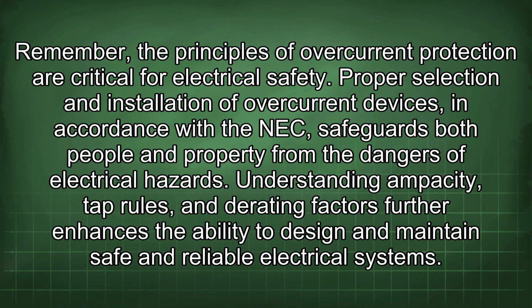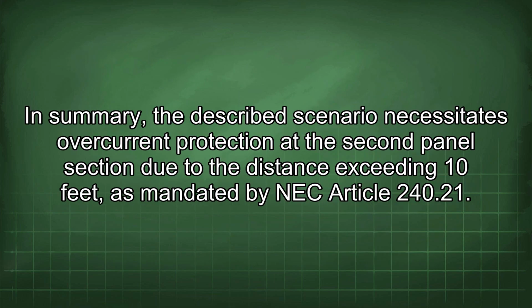Remember, the principles of overcurrent protection are critical for electrical safety. Proper selection and installation of overcurrent devices, in accordance with the NEC, safeguards both people and property from the dangers of electrical hazards. Understanding ampacity, tap rules, and derating factors further enhances the ability to design and maintain safe and reliable electrical systems. In summary, the described scenario necessitates overcurrent protection at the second panel section due to the distance exceeding 10 feet, as mandated by NEC Article 240.21.